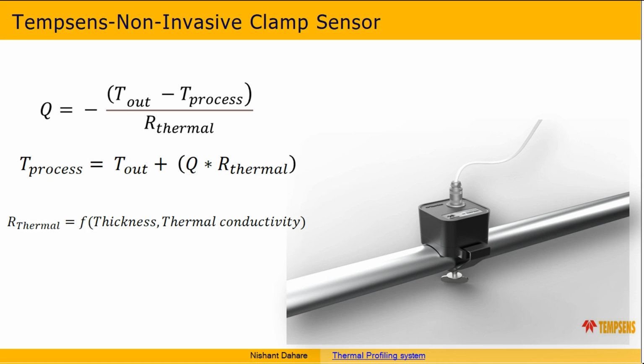So you just need to select the pipe in the software, then it will give you ultimately the accurate results irrespective of the pipe dimension, pipe material and pipe thickness. So this is a basic fundamental. If you know the surface temperature, which is basically T out, you know the heat flux and you know the thermal resistance of the pipe, then you can give the exact temperature of the fluid inside the pipe without any intervention or without any drilling of a hole in the pipe.